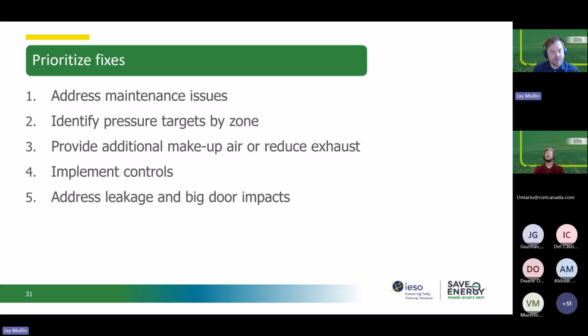Another thing on here, if it's not matching, is zone dampers. Controlling flow between zones can help ensure process areas with the high exhaust get priority air supply. In most industrial sites with heavy exhaust, there are dedicated makeup air units. Ideally, those should be sized for exhaust. But again, sometimes things get moved around, and that makeup air unit may be supplying a lot of that air to a region in your facility that no longer has high exhaust levels. So use dampers or redirect flow to help make sure that's taking place.